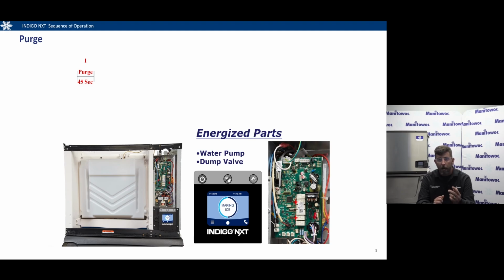So the pump and the dump valve are going to be energized. So you'll see the board there. It's calling out a little red star indicator showing you your LEDs. Those two, the second from the top and the second from the bottom, are going to be energized, letting you know, hey, I'm sending power out to this device.